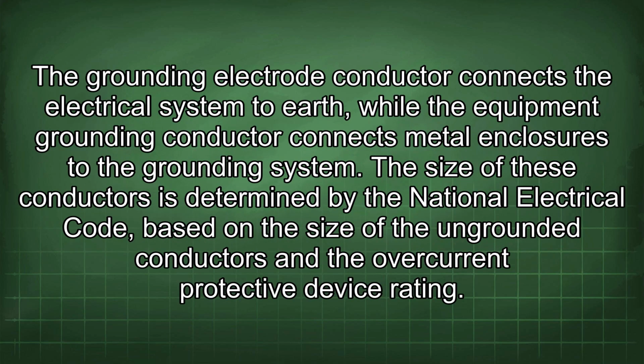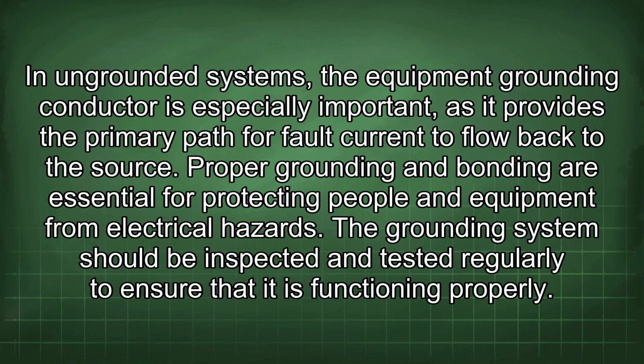The grounding electrode conductor connects the electrical system to earth, while the equipment grounding conductor connects metal enclosures to the grounding system. The size of these conductors is determined by the National Electrical Code, based on the size of the ungrounded conductors and the overcurrent protective device rating. In ungrounded systems, the equipment grounding conductor is especially important, as it provides the primary path for fault current to flow back to the source. Proper grounding and bonding are essential for protecting people and equipment from electrical hazards.